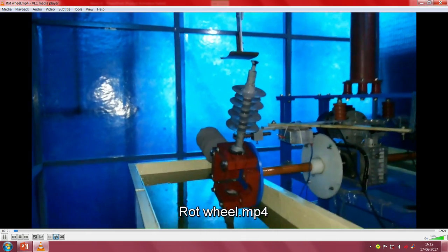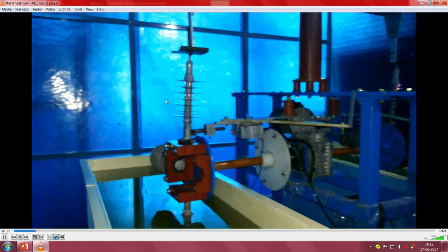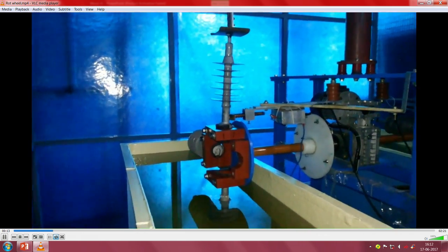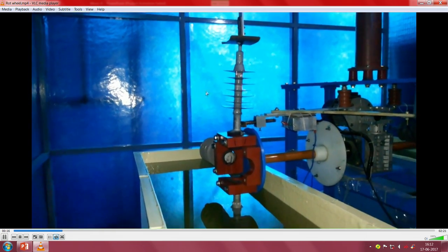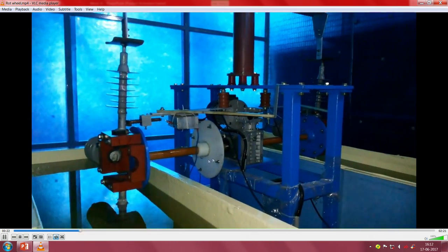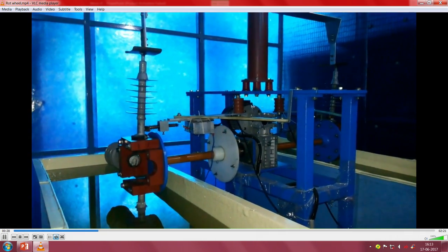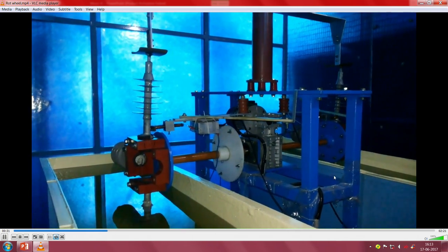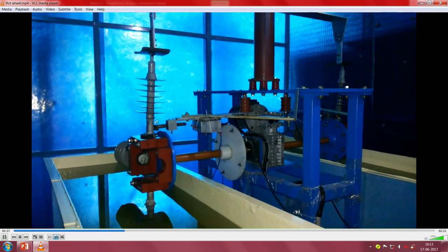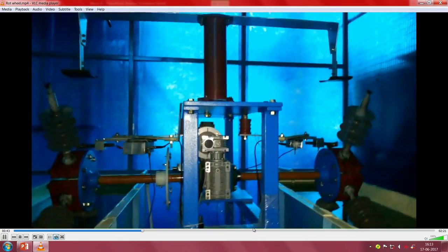Here we can see how the experiment operates in the laboratory. The insulator surface is in contact with the high voltage and discharges or scintillations are visible. This contact lasts for 40 seconds, after which the insulator moves to the cooling period, then dips in the solution again, and comes back to the drip period. Discharges can be seen on either side of the shaft on the insulator surface. Two different tanks are used — one with normal contaminant and one with acidic contaminant — and the surface activity due to electric stress is clearly visible.